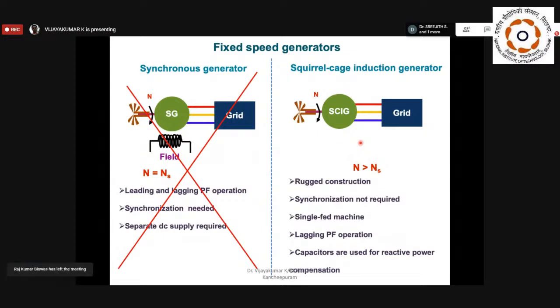Even with these advantages of squirrel cage induction machines, the major disadvantage is lagging power factor operation. Whether it operates as a motor or a generator, it always takes reactive power from the grid. If you always take reactive power from the grid, there are power quality issues on the grid side, so that is not advisable.